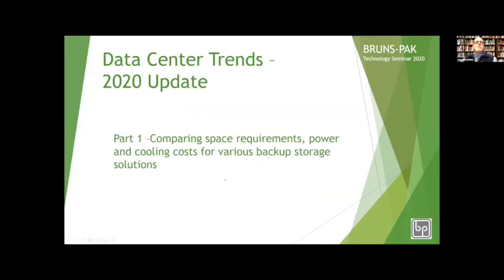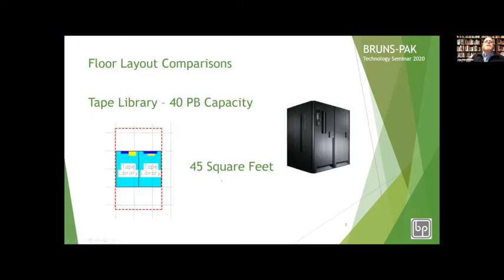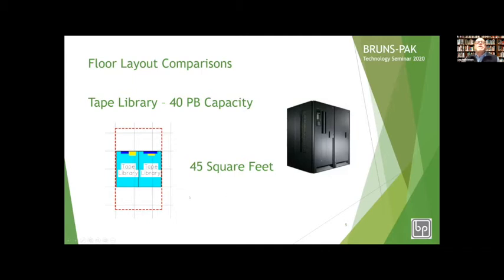Part one: comparing space requirements, power, and cooling for various backup storage solutions. I'm comparing a 40 petabyte capacity solution. This is an IBM tape library — two frames, a robot goes up and down on a track, grabs a tape cartridge, puts it in a drive, reads it, and puts it back. The cartridges are double-stacked inside like a PEZ dispenser. This two-frame solution takes up 45 square feet of space with service clearance overlaid onto a two-foot raised floor.